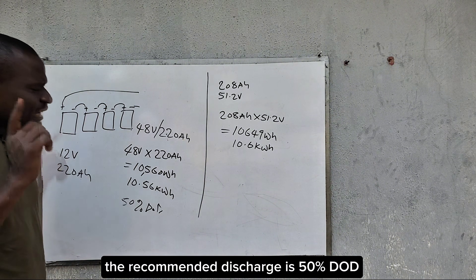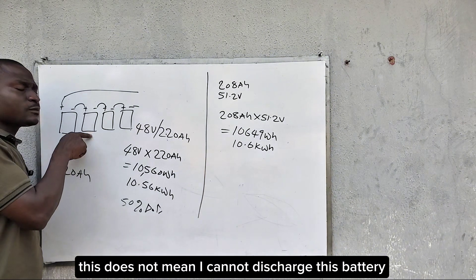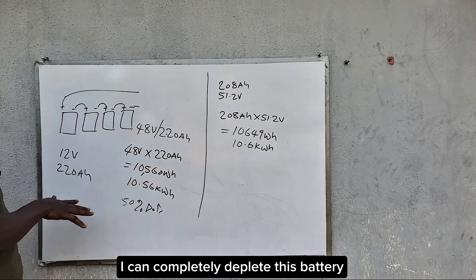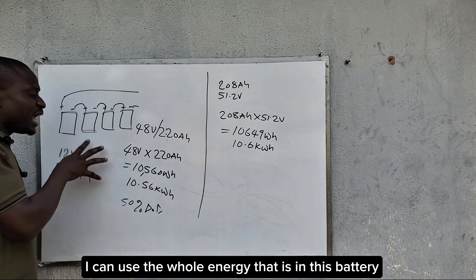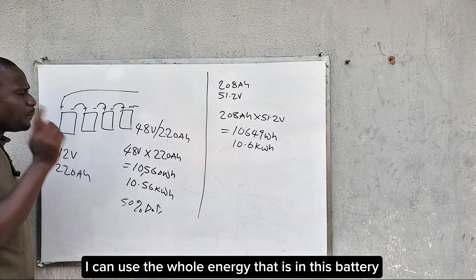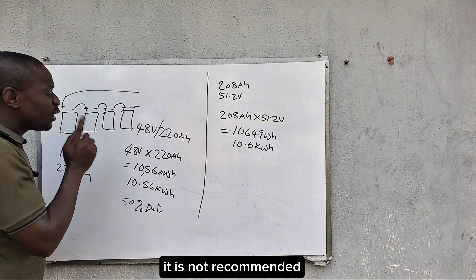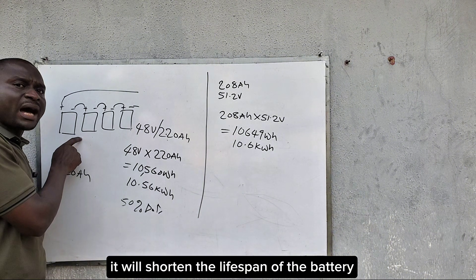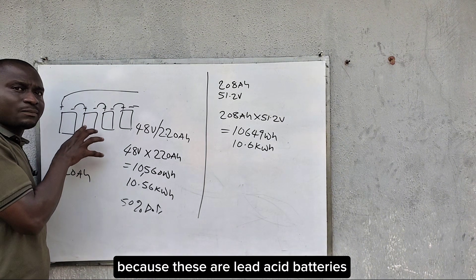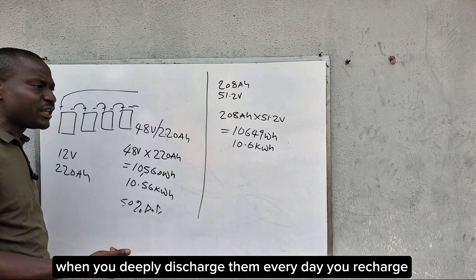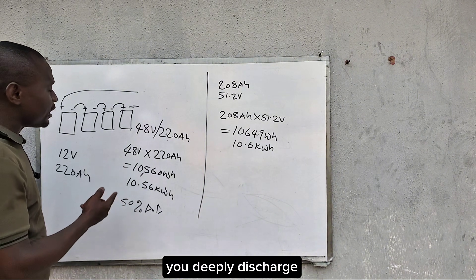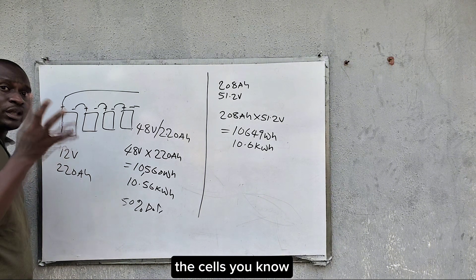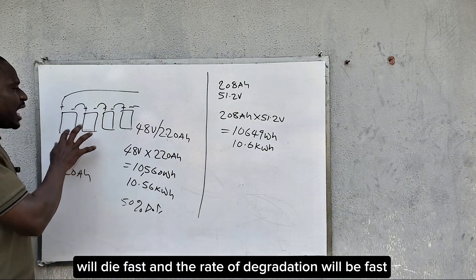When we say 50% DoD recommended, this does not mean I cannot discharge the battery up to 100%. I can completely deplete it and use all the energy in it. But since it is a lead acid battery, it is not recommended, because if I do that every day it will shorten the lifespan. When you deeply discharge lead acid batteries every day, the cells will die fast and the rate of degradation will be fast.